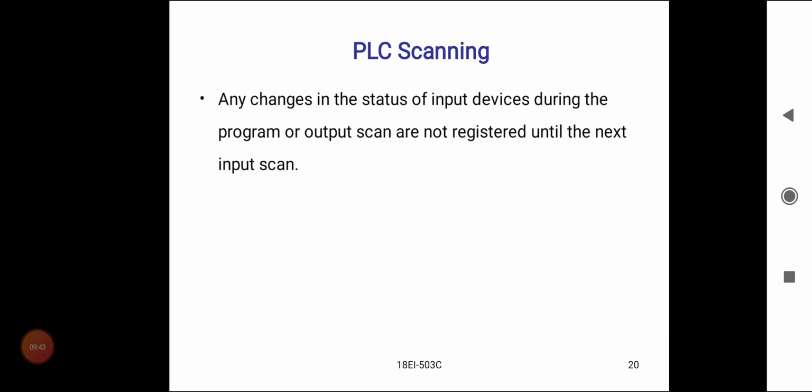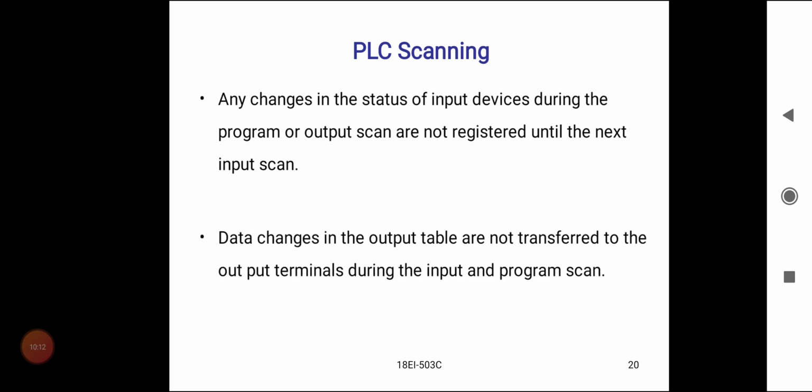Any changes in the status of the input devices during the program or output scan are not registered until the next input scan. Data changes in the output table are not transferred to the output terminals during the input and program scan.